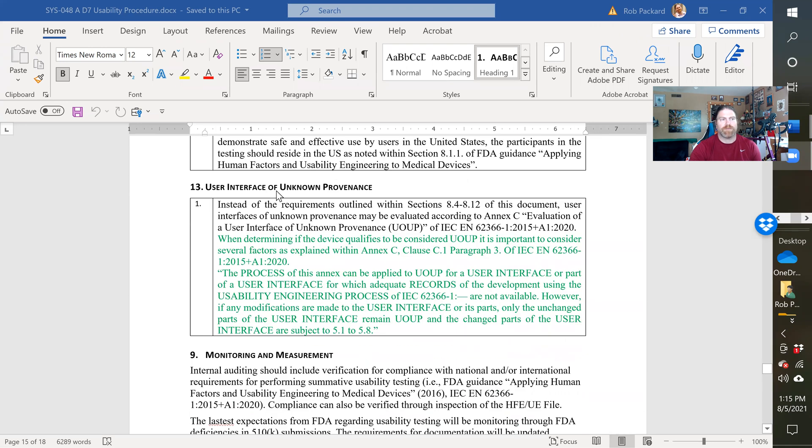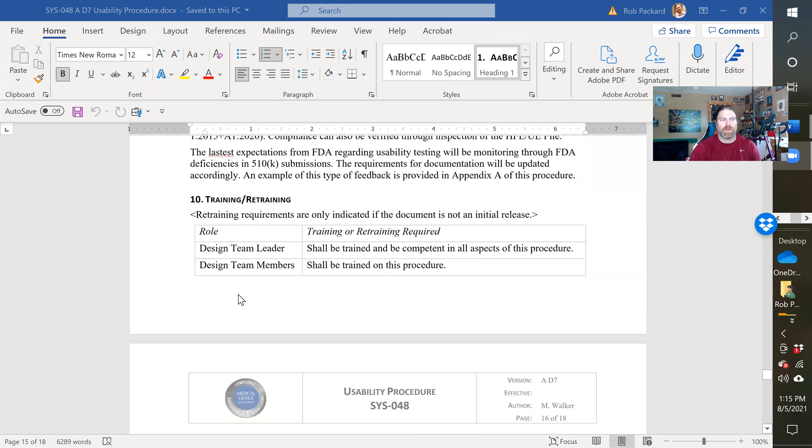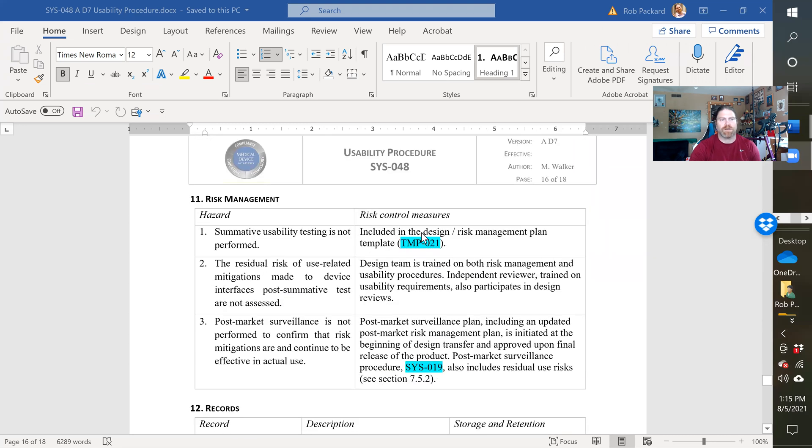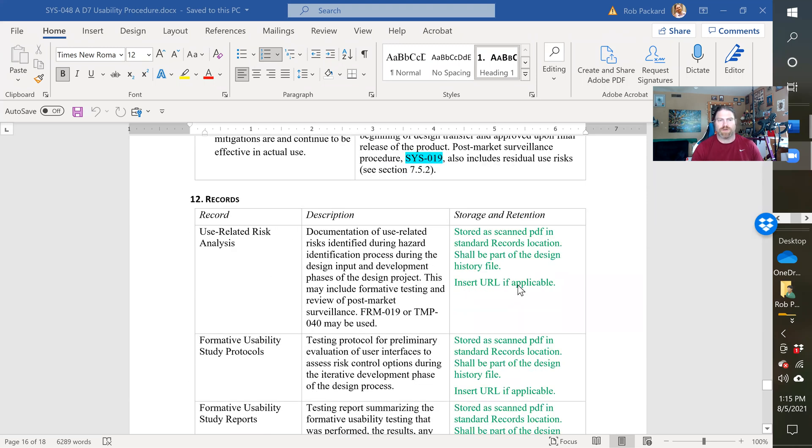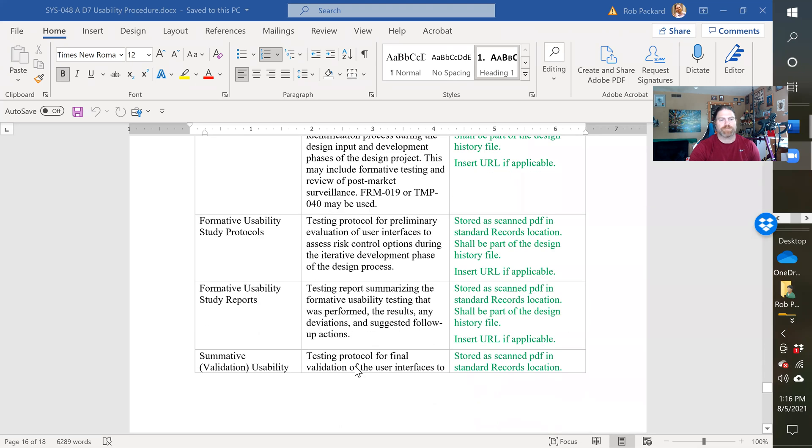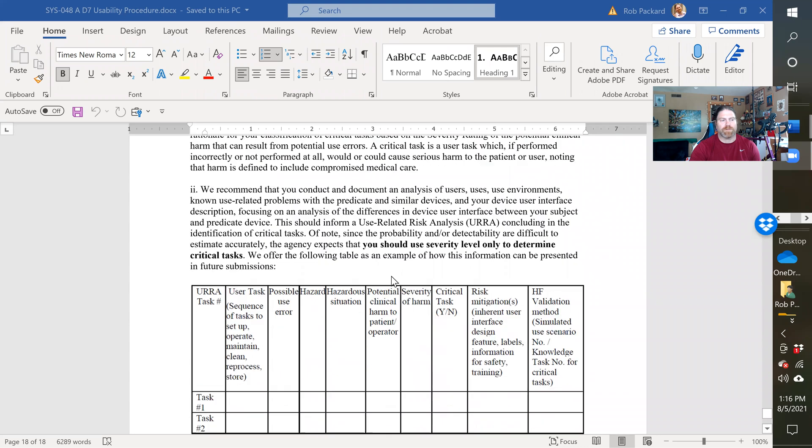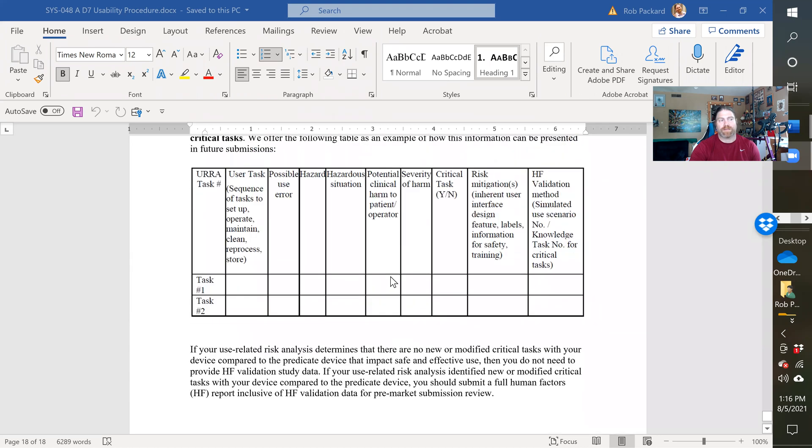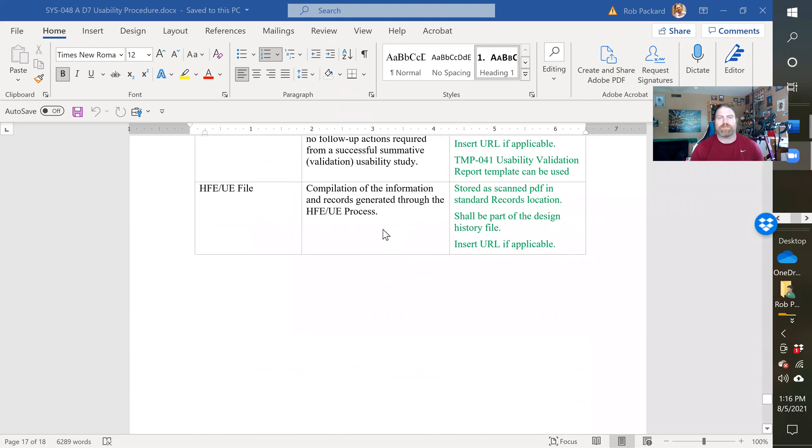And then a section dedicated to user interface of unknown provenance, this would be for legacy systems. We have monitoring and measuring of this procedure, which would be typically through auditing of the process, but we also have here a comment about the Appendix A, which is an example of deficiencies provided by the FDA on 510K submissions. We have a training and retraining section, risk management for this procedure to make sure it's more consistent, and we've added the new additional templates as records here. So we have the user related risk analysis and the two possible templates that you might use, and the other particular records here as well that keeps on going. And then on the last page we have our example that we provide, and that's actually a copy and paste right from a deficiency with confidential details scrubbed out from that submission.